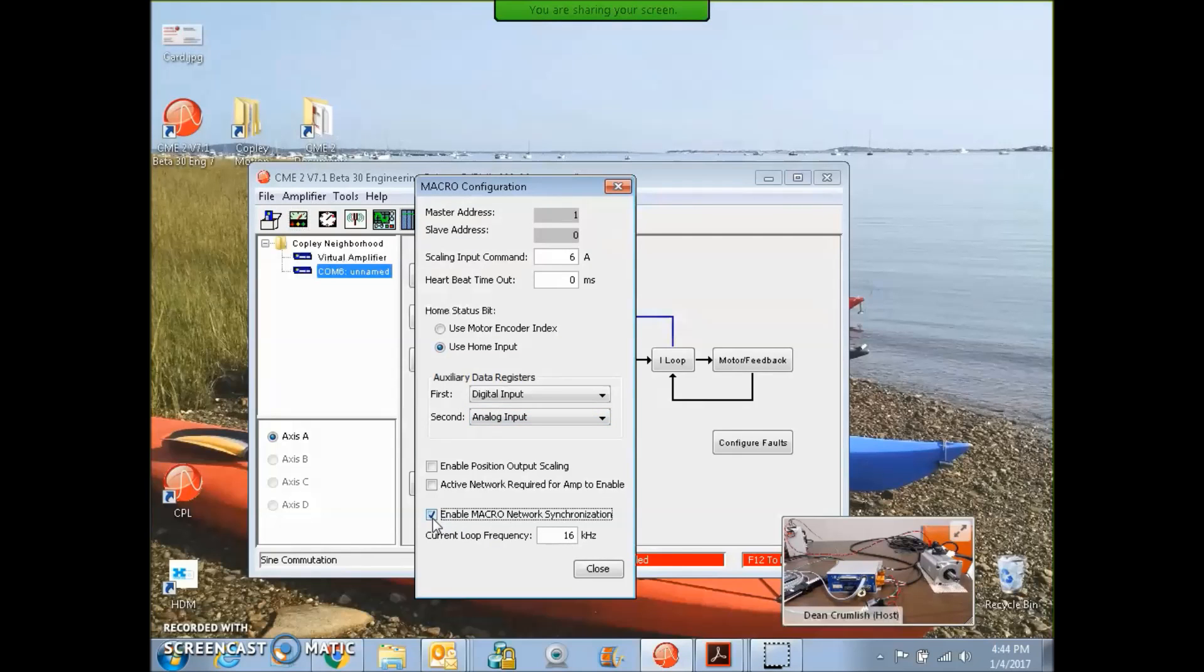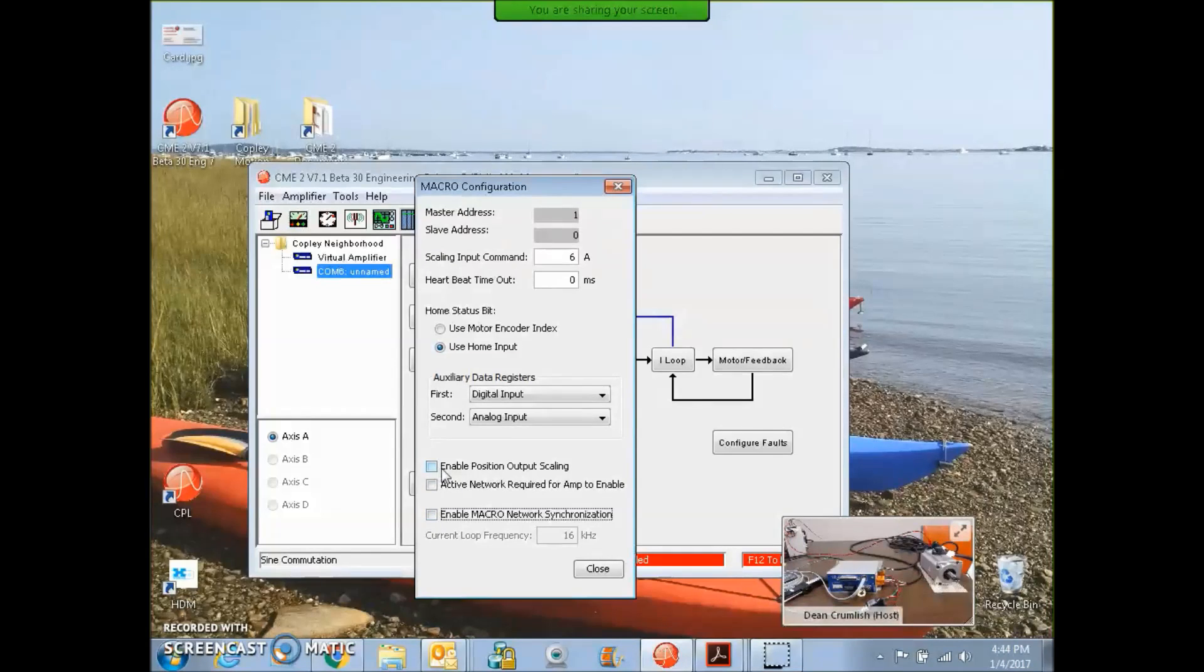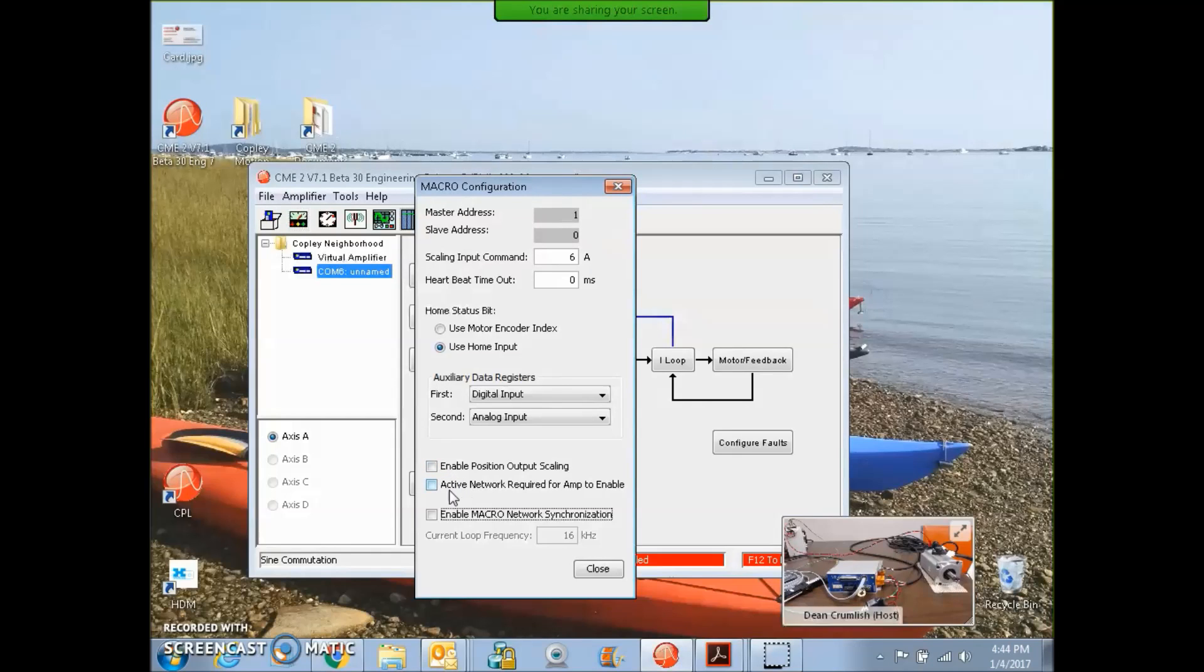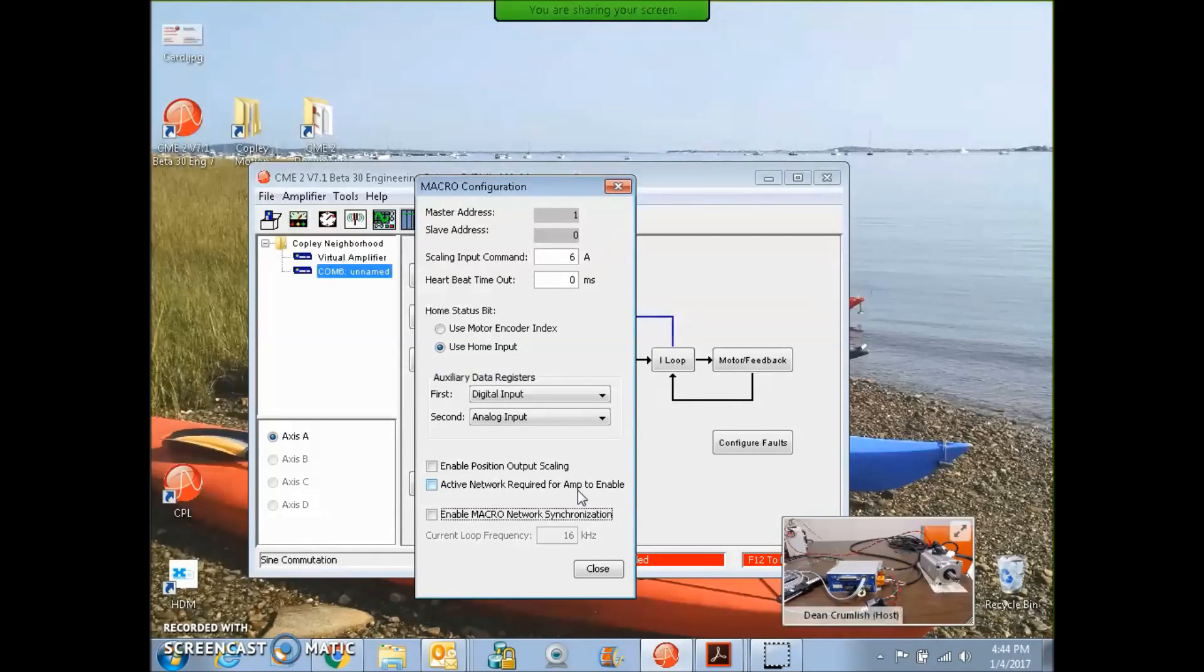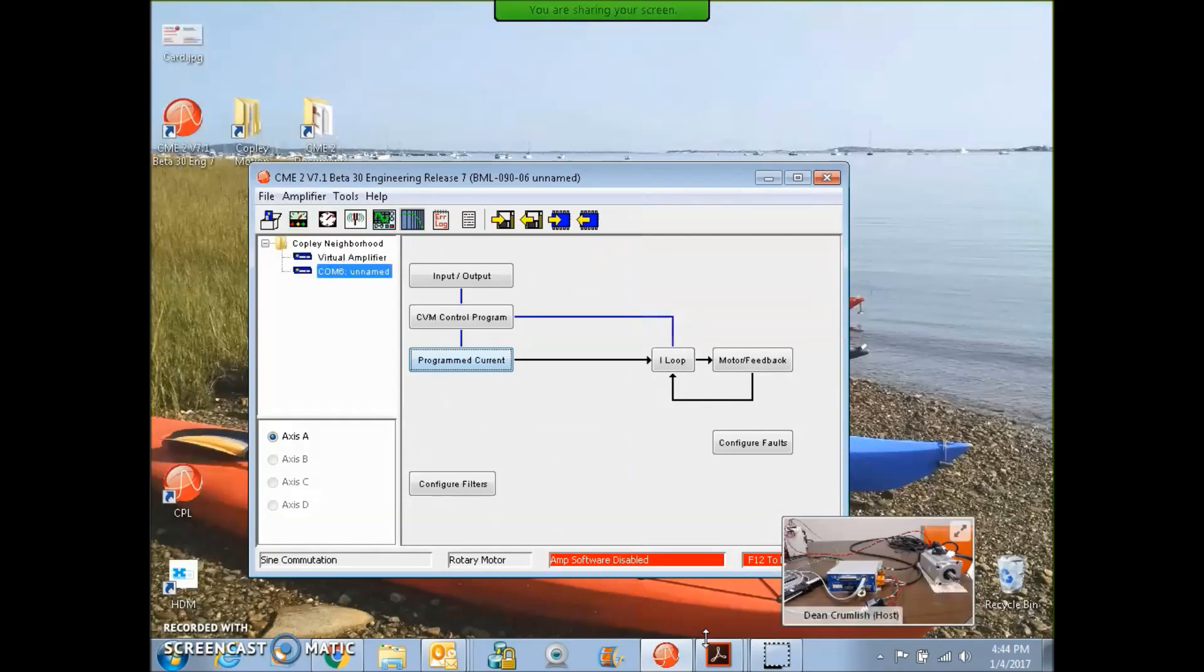Just be careful when you change the frequency. You'll have to retune the current loop again. Enable position, output scaling. Maybe we need that for this really big encoder. Active network required for Amp to enable. That's just a nice feature. It lets the master come in and configure it.